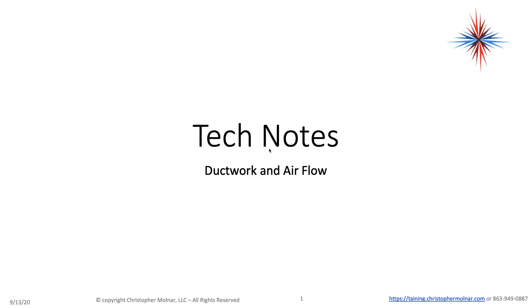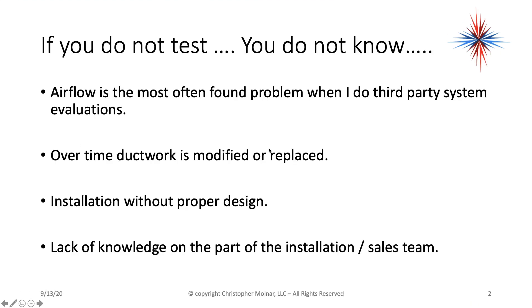So why do we care about airflow? Basically because if you do not test, you do not know. Airflow is the most often found problem when I do third-party system evaluations. Part of the problem is that over time ductwork is modified, might be replaced, might be damaged. Sometimes we do installations without proper design, and sometimes there's a lack of knowledge on the part of the installation and sales team.